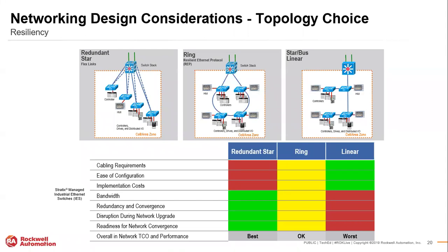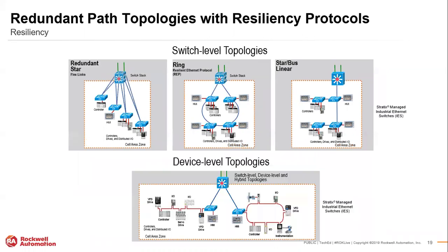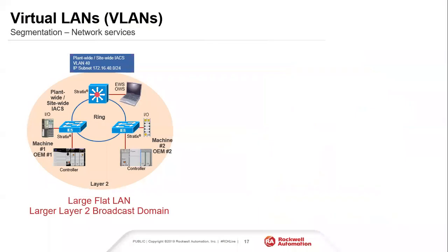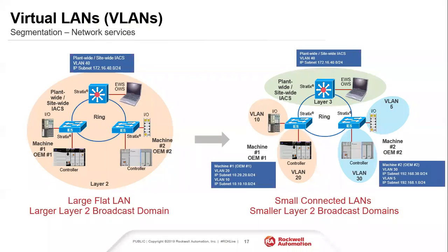So you can. The idea there, topology wise, let's say we have 5 panels and everything's connected at 100 meg. And then I consolidate everything to a top end network. So if these connections are all 100 meg, and I want to consolidate everything and tie into a gig network once I'm at the top, and everything above is now a gig, it doesn't minimize the 100 meg, but the expectation is the information that I'm getting from my point IO is never faster than 100 meg.